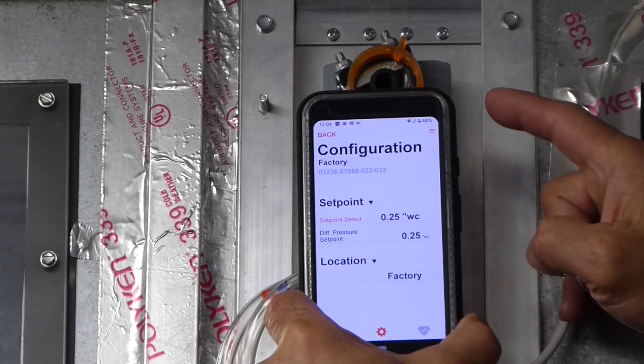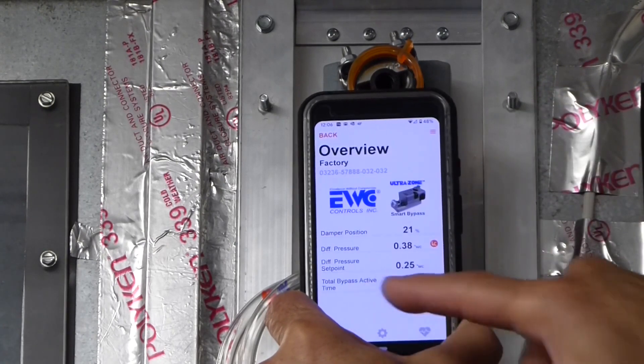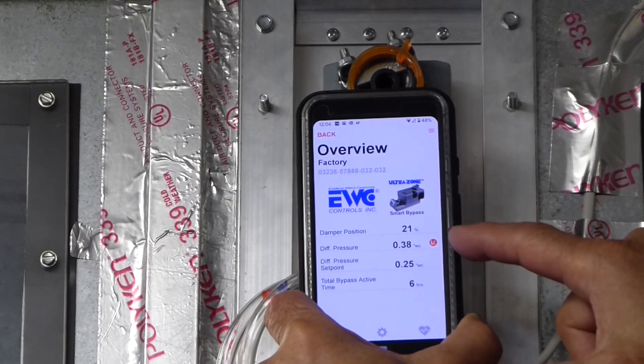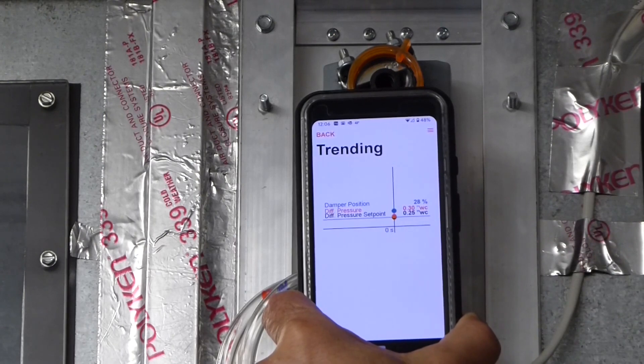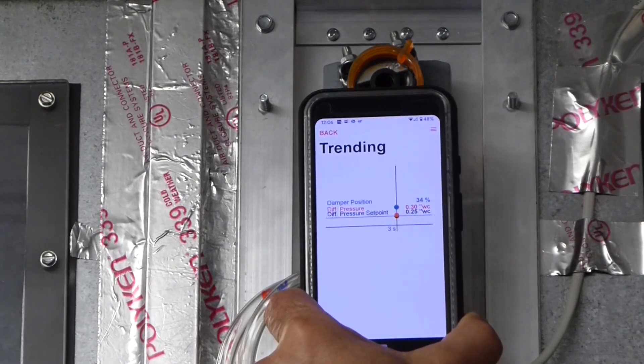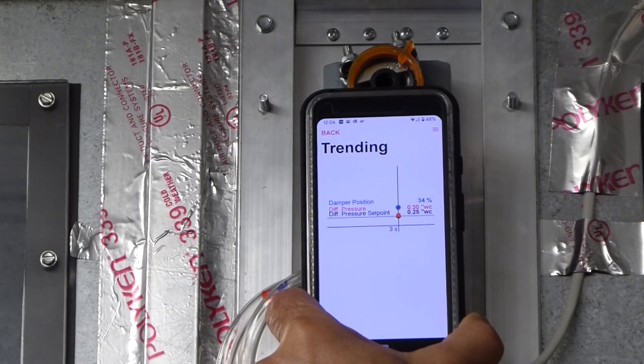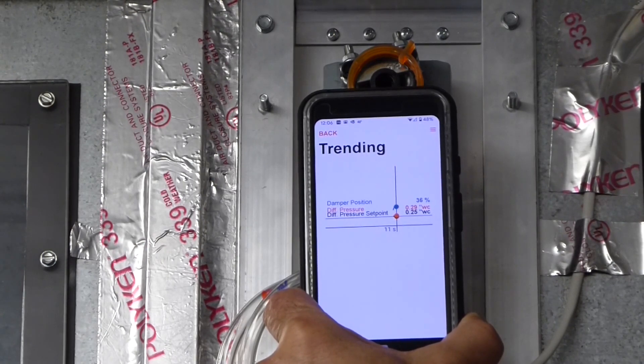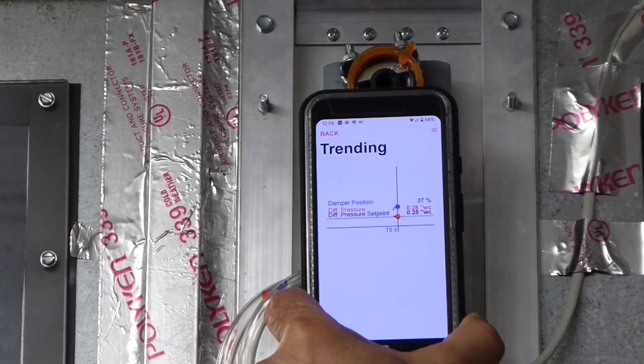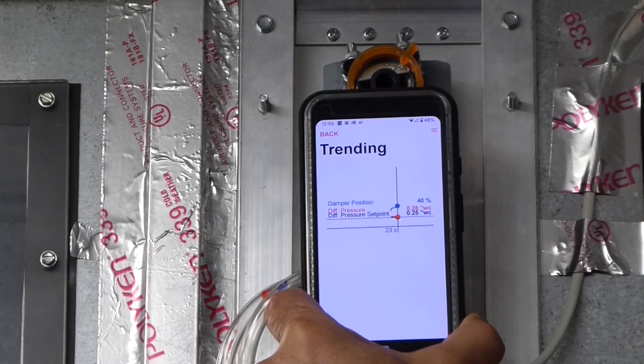Now, select the trend icon to observe the new parameters and create an accurate graph of the HVAC system's static pressure versus the SBD-2's new static pressure set point and damper position in real time. This is, of course, extremely valuable information. Note that as the damper changes position, the actual static pressure of the HVAC system gets closer to the SBD-2 set point.